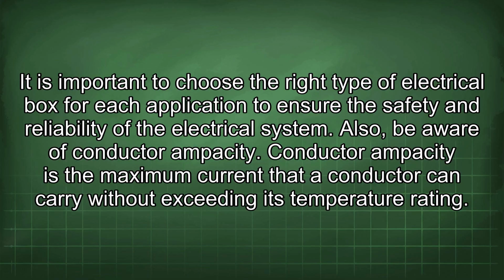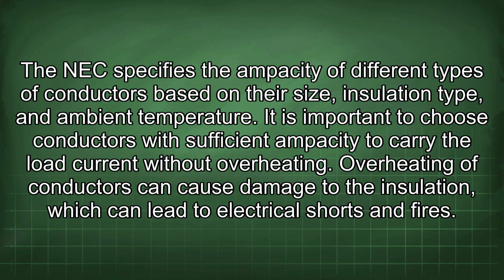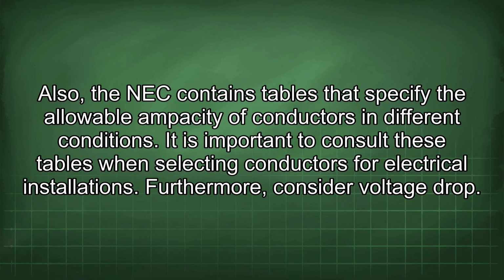Also, be aware of conductor ampacity. Conductor ampacity is the maximum current that a conductor can carry without exceeding its temperature rating. The NEC specifies the ampacity of different types of conductors based on their size, insulation type, and ambient temperature. It is important to choose conductors with sufficient ampacity to carry the load current without overheating. Overheating of conductors can cause damage to the insulation, which can lead to electrical shorts and fires. Also, the NEC contains tables that specify the allowable ampacity of conductors in different conditions. It is important to consult these tables when selecting conductors for electrical installations.